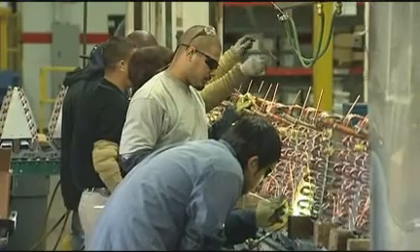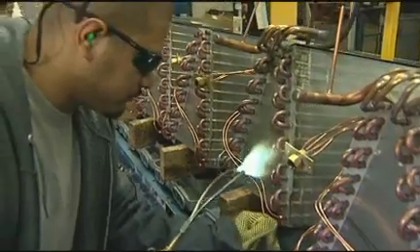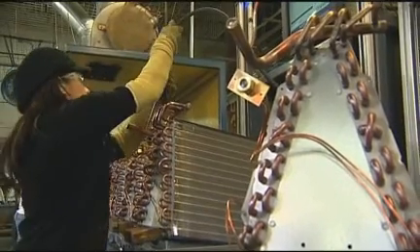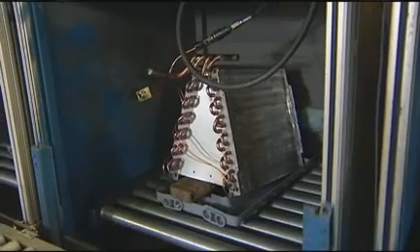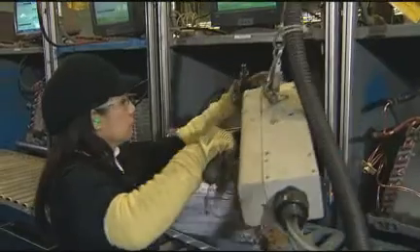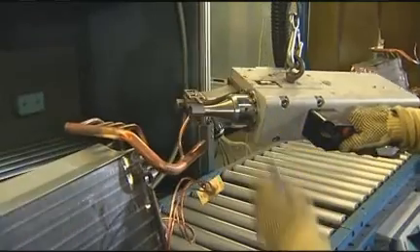Brazing is one of the most important parts of this whole process. Not everybody can do brazing. There are Goodman certified brazers who are certified once a year. Once the brazing operation is complete, the coil comes right over here through the cooling chamber. The braze joint gets cooled down and it goes to the test chambers. The coils are being tested at 455 PSI pressure. Once it passes the test, the coil gets pinched off and it becomes a sealed system.